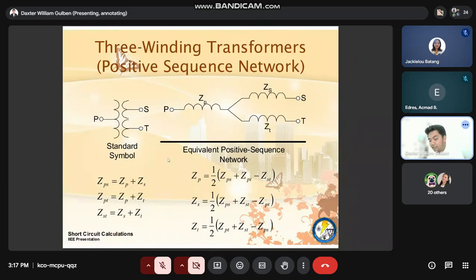These are the transmission transformers that are 3-winding. For example, the input P is, let's say, 69 kilovolts. The outputs are two: the tertiary at 138 kilovolts and the secondary at 230 kilovolts. So those are the kinds of transformers, and there are two outputs, so you have to consider that also in your system analysis. At the same time, you can also compute your ZP, ZS, ZT in reverse with this one. This is the computation. Okay?